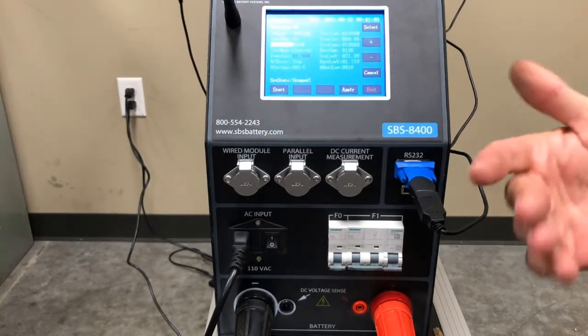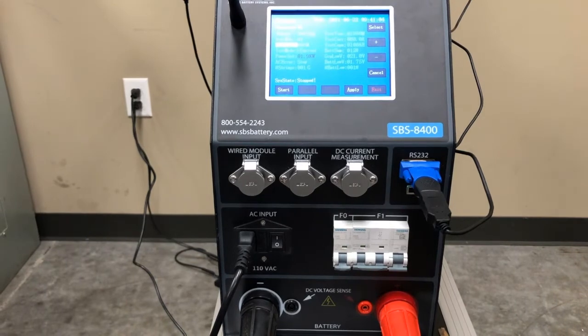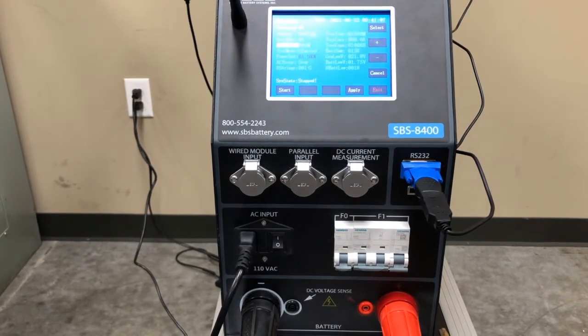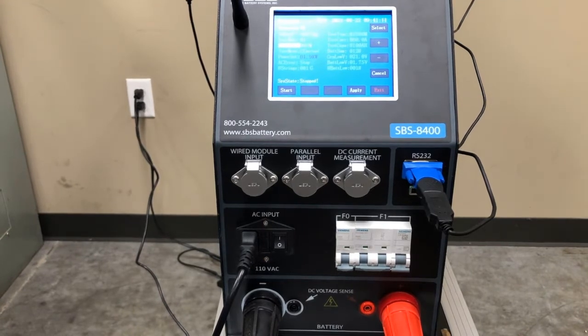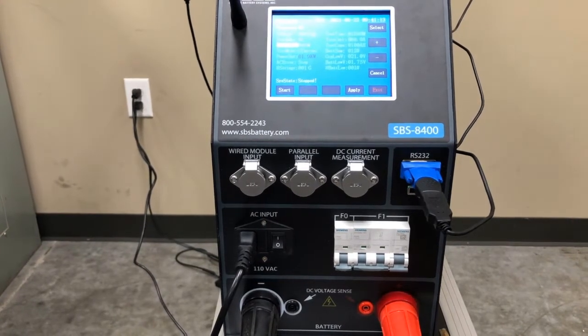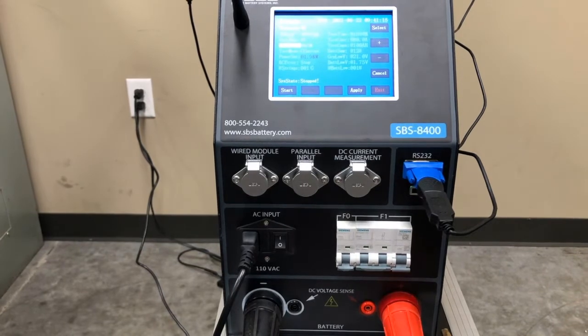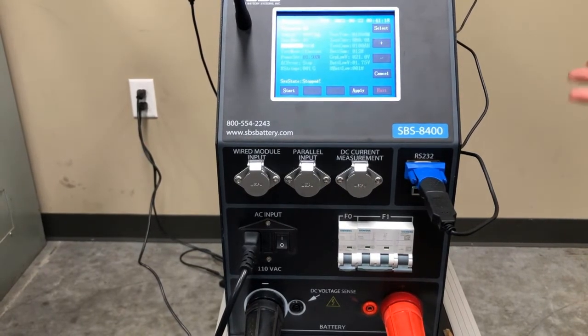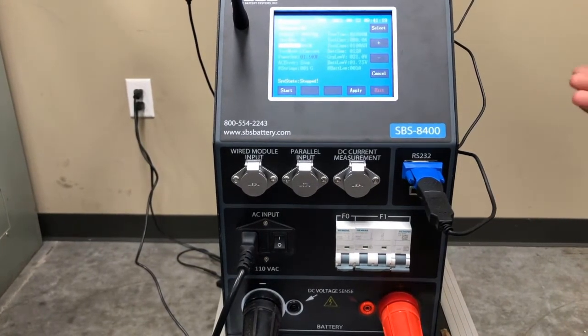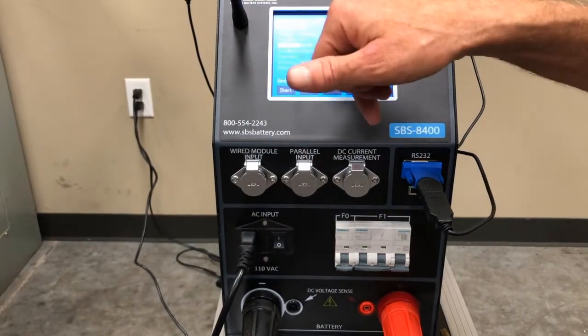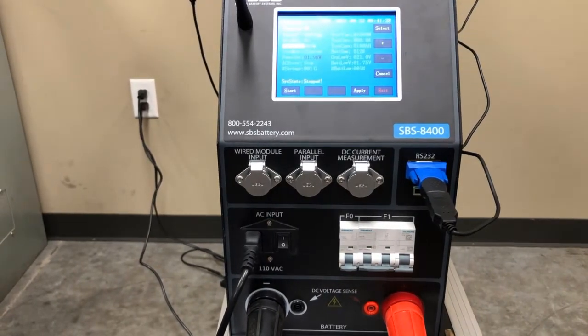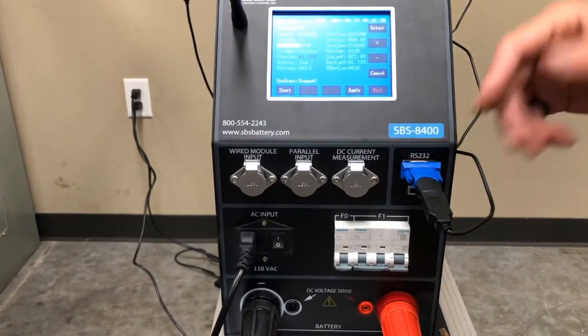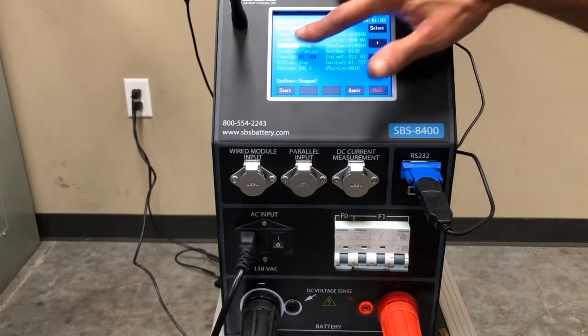I usually save data every 10 minutes on a 1 hour test. On an 8 hour test, I'm only going to save data every 15 minutes. Okay. You can save data every minute if you want, but it just makes for a huge, gigantic report that can be 30 pages long. So over an hour, this is going to give me a starting point and ending voltage, and it's going to give me 12 voltage levels during the performance of that test. Okay. So every 5 minutes is okay.